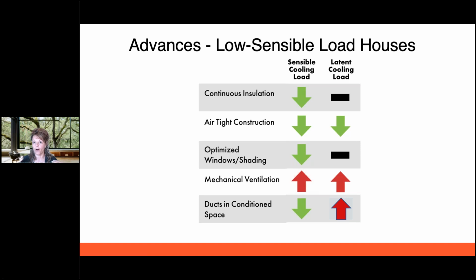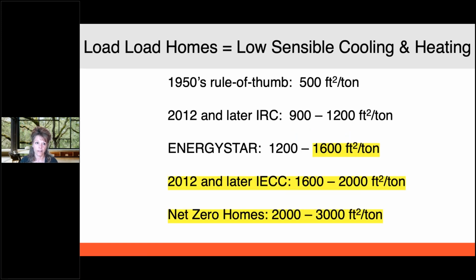Now we're trapping all of any potential leakage from our duct systems into the house, which is going to reduce the runtime, which is great, but also we're not going to run as long and remove that moisture. So low load homes, the definition of a low load home for low sensible cooling starts at about 1,600 square foot per ton. And then as you can see, our building codes are making us tighter.